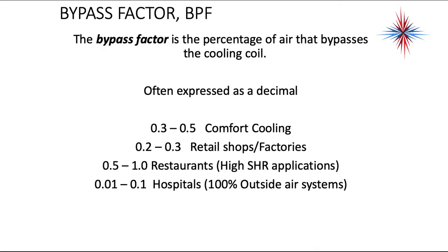We also have the bypass factor. The bypass factor, or BPF, is the percentage of air that bypasses the cooling coil, often expressed as a decimal. For comfort cooling it's between 0.3 and 0.5. For retail shops and factories it's 0.2 to 0.3. For restaurants it's 0.5 to 1.0. And for hospitals, which use 100% outside air, it's 0.01 to 0.1. Just a rule of thumb.